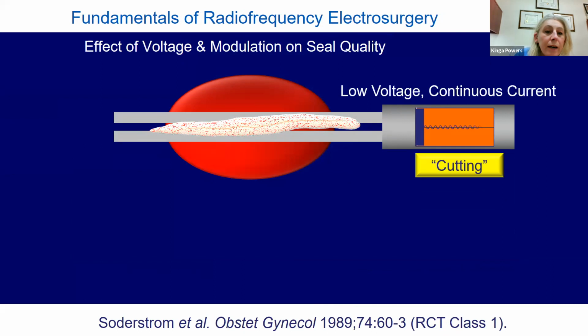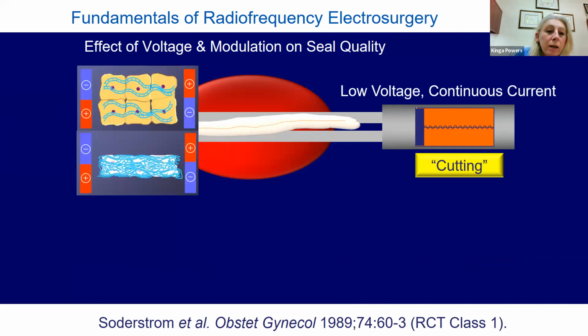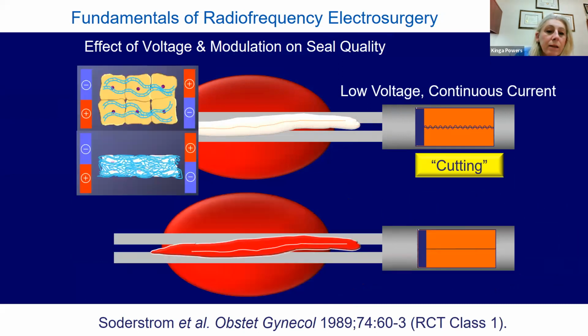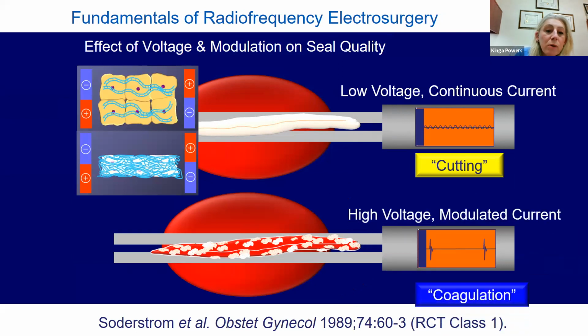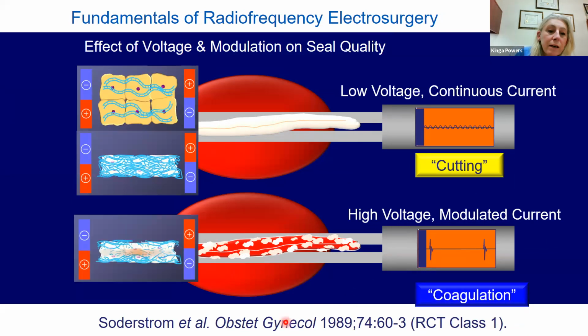This is your cutting mode, and the coag mode with high voltage results in an uneven, less effective seal of the blood vessel. It also causes caramelization of the sugars inside the cells, creating a sticking effect, so it's hard to open the forceps. In fact, when you open the forceps, sometimes you disrupt the coagulum and stickiness, and it actually reopens the vessel—so it's not as effective.